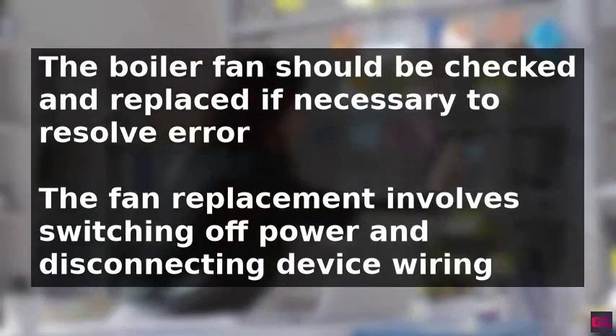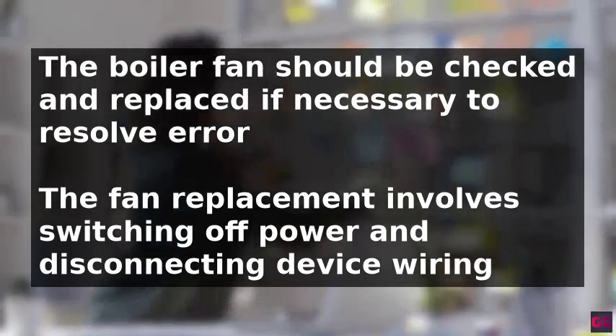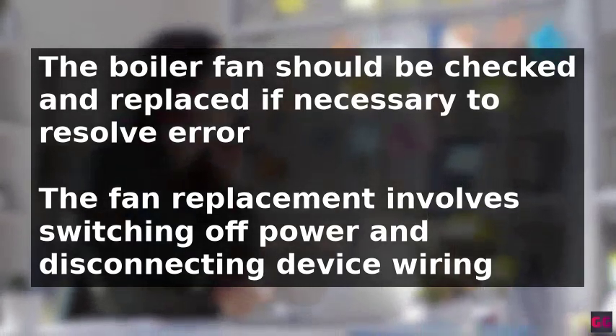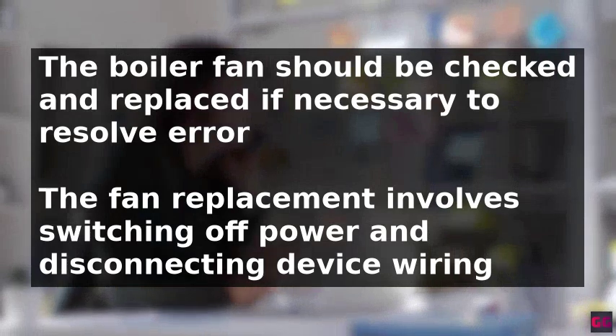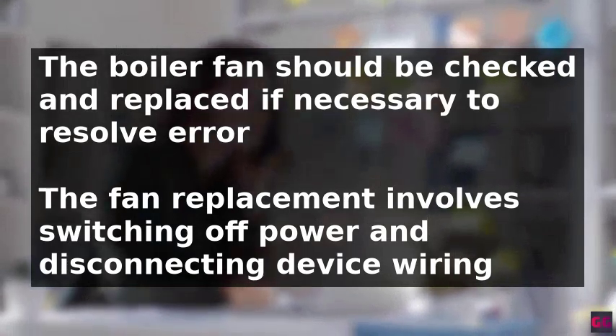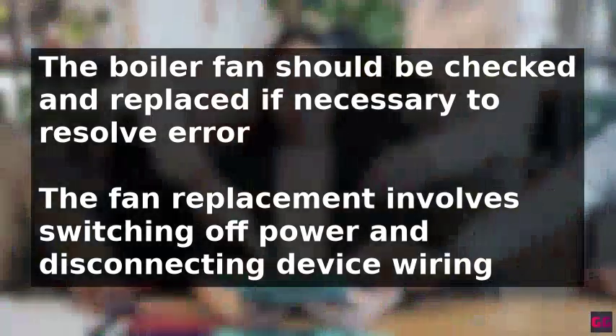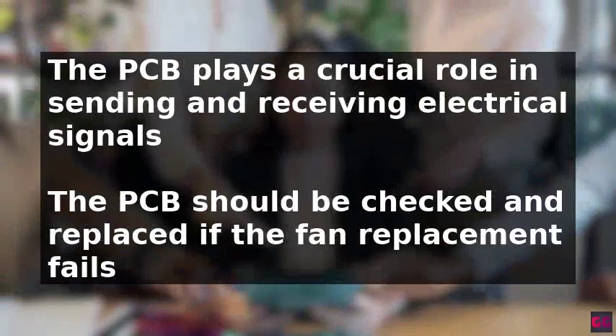disconnecting the device wiring, removing the fan, blowing out any dust from the fan housing, and then reconnecting the wiring harness. After replacing the fan, the boiler should be turned back on to check if the issue is resolved.